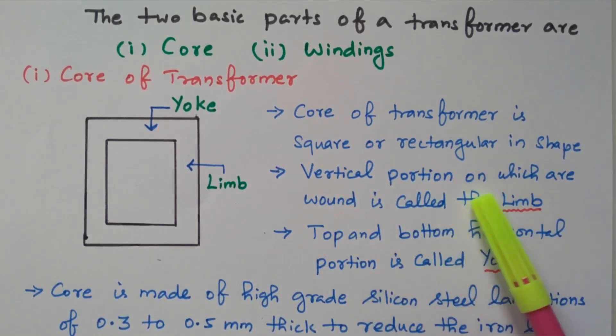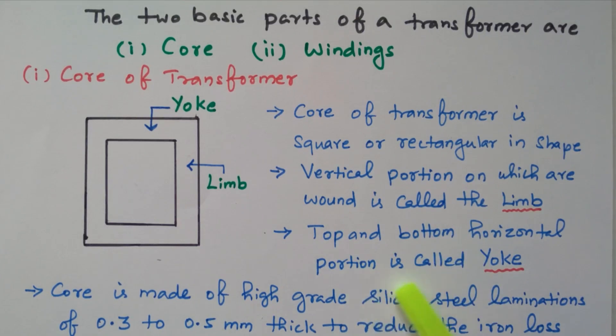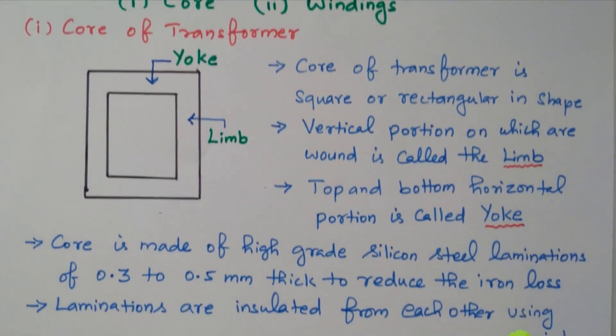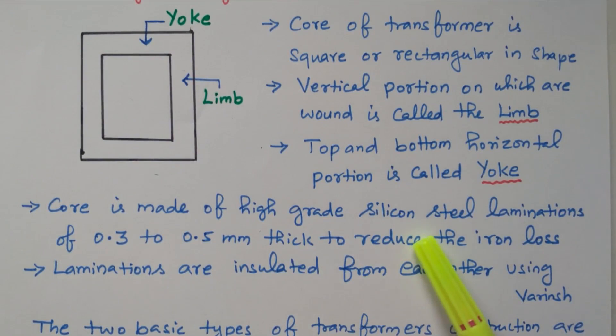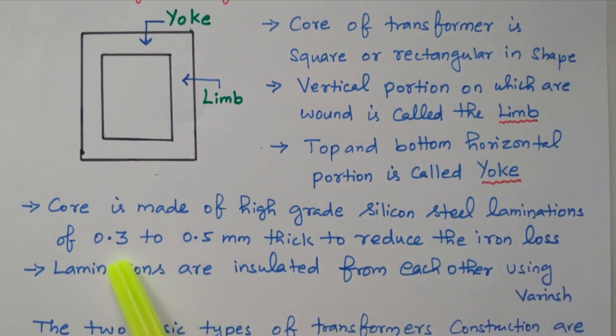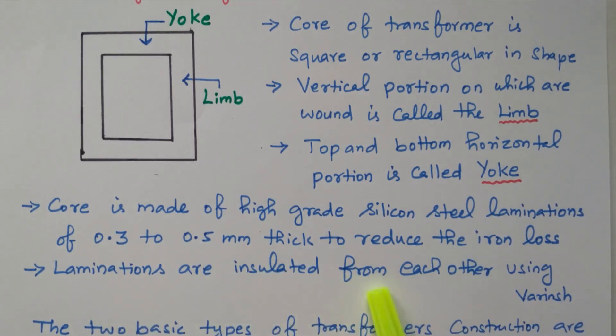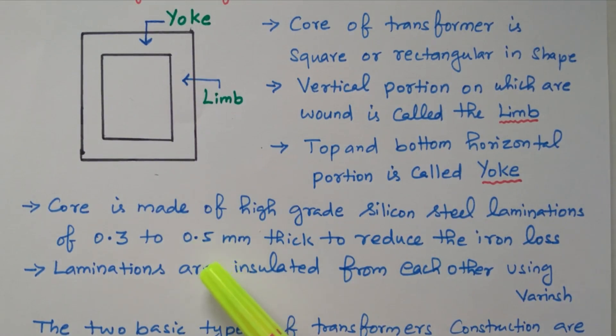The vertical portion on which the winding is wound is called the limb. The top and bottom horizontal portion is called the yoke. The core is made of high grade silicon steel laminations of 0.3 to 0.5 millimeter thickness — very thin sheets to reduce the iron loss. The laminations are insulated from each other using varnish, then compressed together.